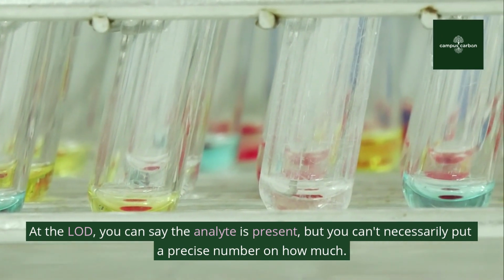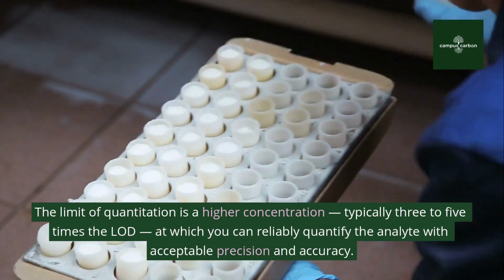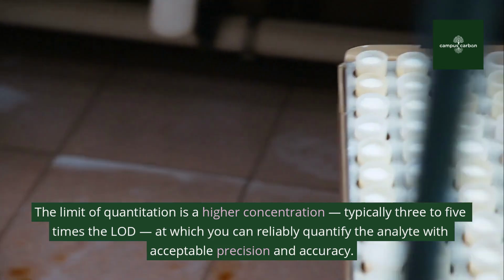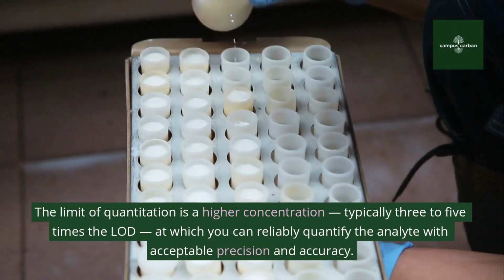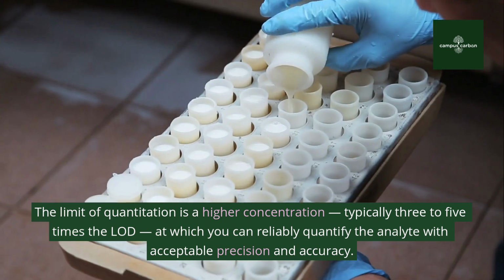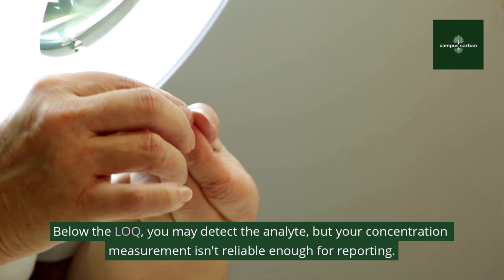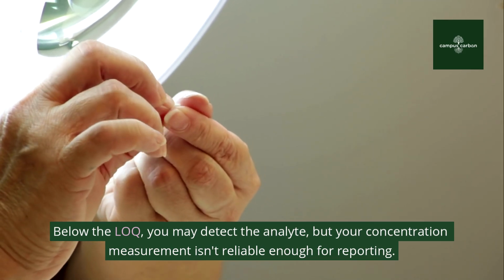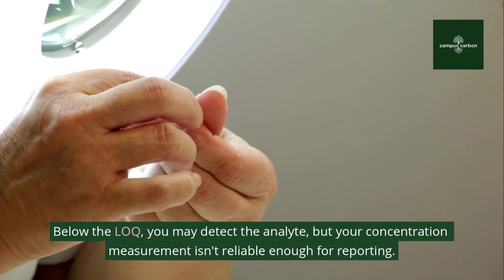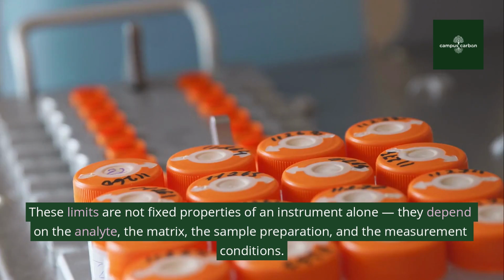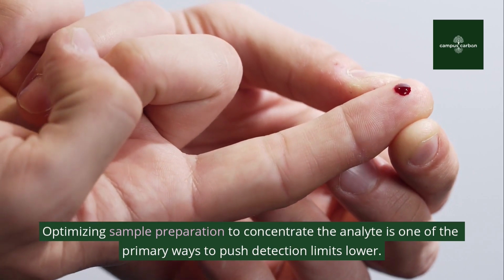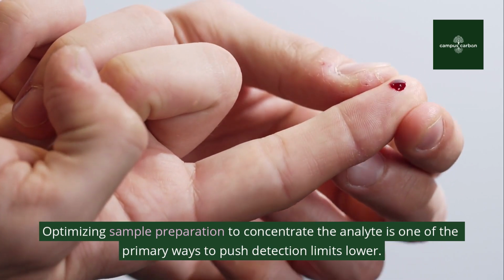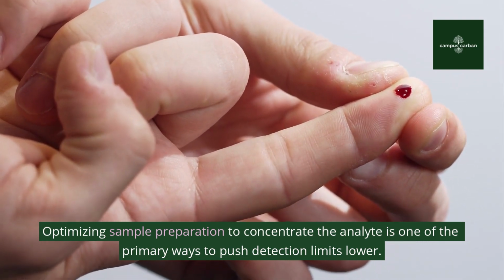The limit of quantitation is a higher concentration, typically 3 to 5 times the LOD, at which you can reliably quantify the analyte with acceptable precision and accuracy. Below the LOQ, you may detect the analyte, but your concentration measurement isn't reliable enough for reporting. These limits are not fixed properties of an instrument alone. They depend on the analyte, the matrix, the sample preparation, and the measurement conditions. Optimizing sample preparation to concentrate the analyte is one of the primary ways to push detection limits lower.